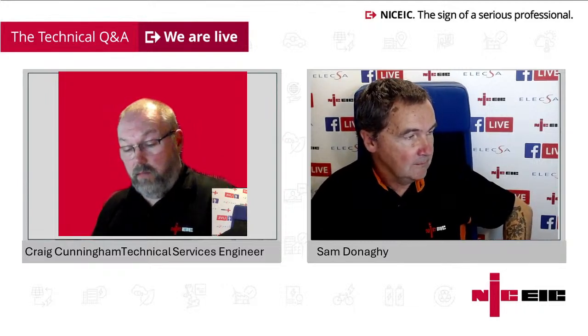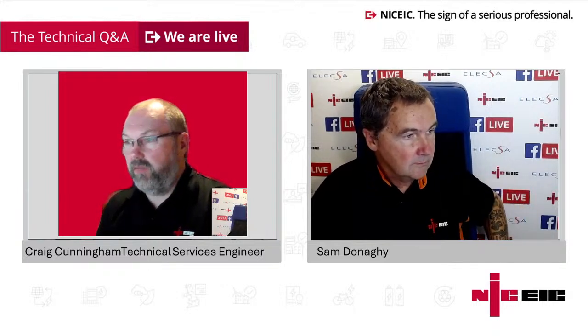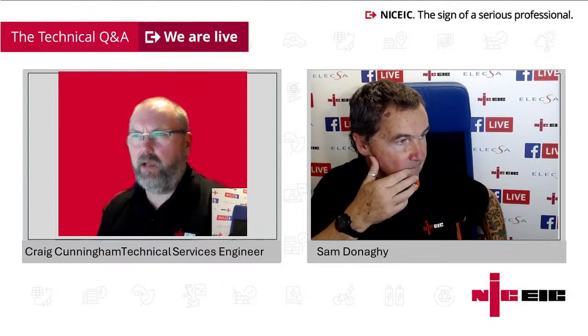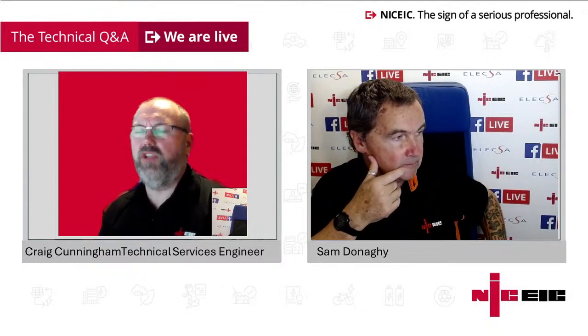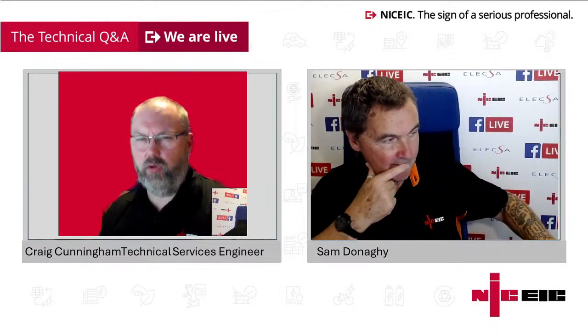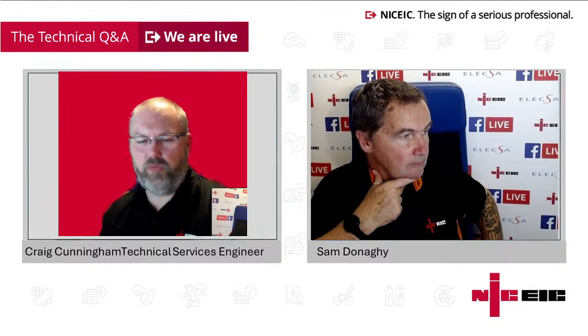Would you add anything to that, Craig? Strange one - no, I'd agree with you exactly. The RCD has to disconnect both line and neutral. So unless they're referring to an old redundant circuit to an outbuilding or something that they were adding or altering to, but in general terms I'd agree - normally it's a new circuit from the origin or from the distribution board.